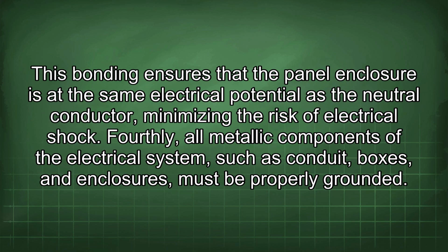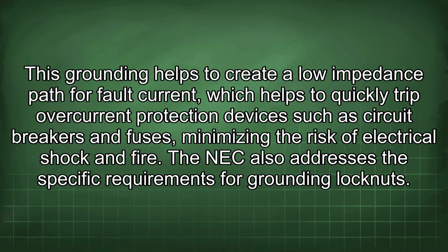This bonding ensures that the panel enclosure is at the same electrical potential as the neutral conductor, minimizing the risk of electrical shock. Fourthly, all metallic components of the electrical system, such as conduit, boxes, and enclosures, must be properly grounded. This grounding helps to create a low impedance path for fault current, which helps to quickly trip overcurrent protection devices such as circuit breakers and fuses, minimizing the risk of electrical shock and fire.